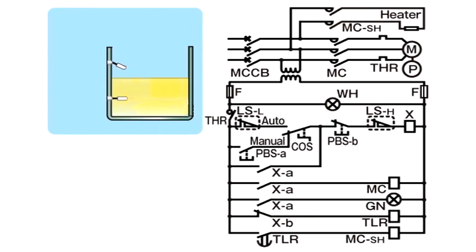If the liquid level falls gradually while the pump is stopped, the L-S-H float goes down and the L-S-H relay is turned on again. However, the motor remains stopped because the X-coil is not excited. If the liquid level falls even further and the L-S-L float also falls, the L-S-L relay turns on.